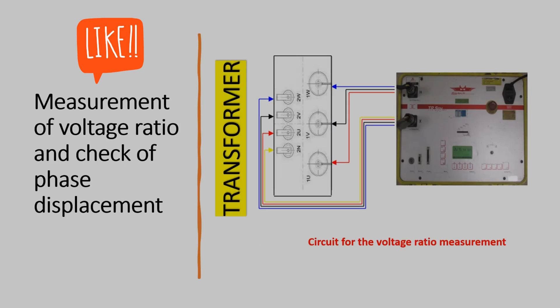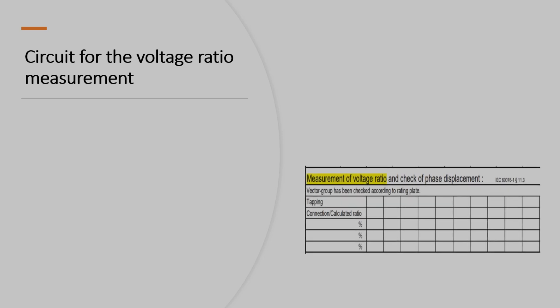This is the circuit of the voltage ratio measurement. This is an example of measuring voltage ratio from vector group, tapping, and connection calculated based on the percentage.